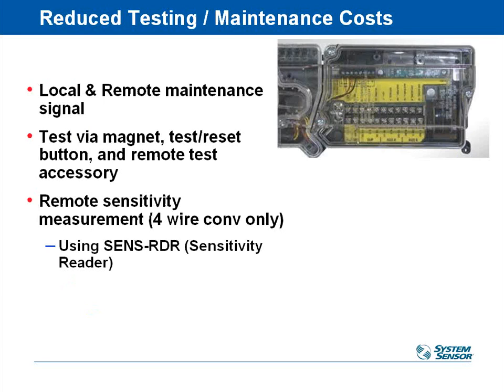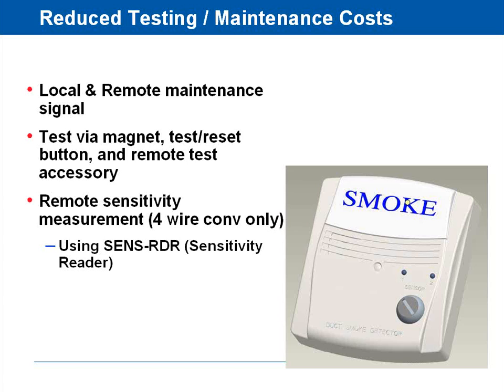Testing these guys can be done several different ways. You can test it with a magnet, which is a very common way for most manufacturers to test them. Obviously, it only tests the electrical circuitry. It doesn't test the smoke detector head itself. It just tests to see if you have a complete electrical connection and your air handler shuts down like you expect and your alarms go off like you expect and all that good stuff. You can also test it with a test button that's on the front of the plastic, so you can do it that way. And if you have a remote accessory station, you can test it that way. And then, of course, if you want to test the full functionality, you'd have to do it with a smoke test in the duct to actually test the detector head itself.